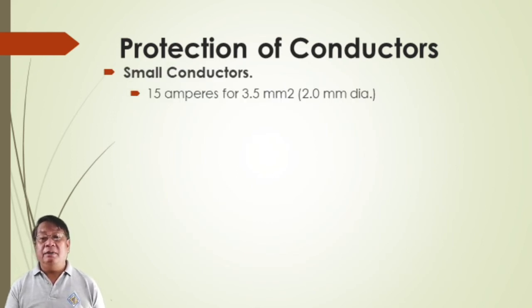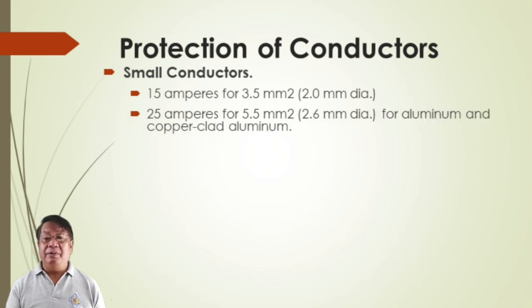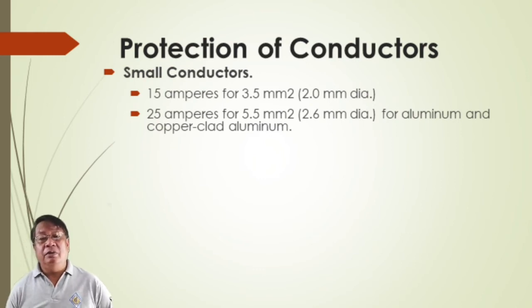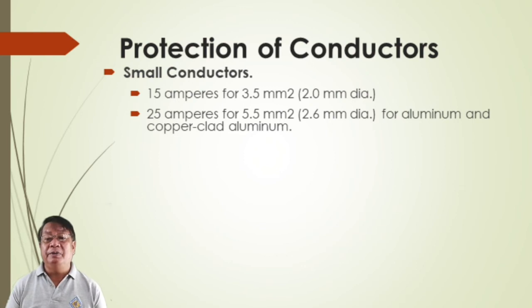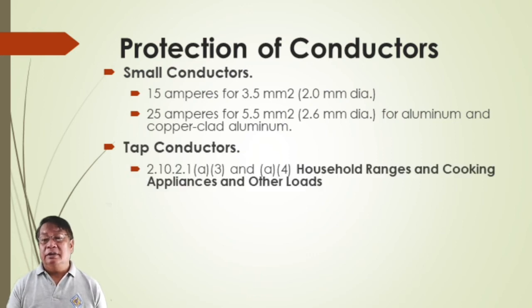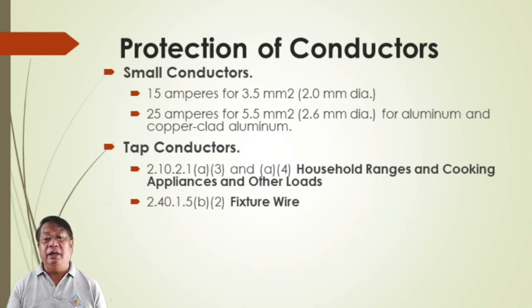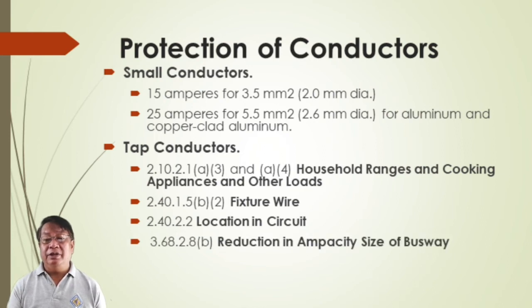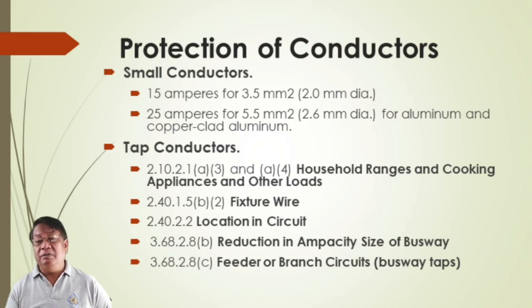For aluminum small conductors: 15 amperes for 3.5 mm² and 25 amperes for 5.5 mm². For house ranges, cooking appliances, and other loads, refer back to Table 2.10.2.1. Standard ampere ratings for fuses and fixed-trip circuit breakers available in the market include: 15, 20, 25, 30, 35, 40, 45, and so on — possibly up to 6,000 amperes.